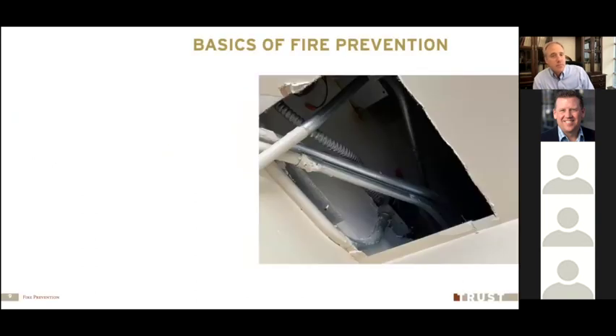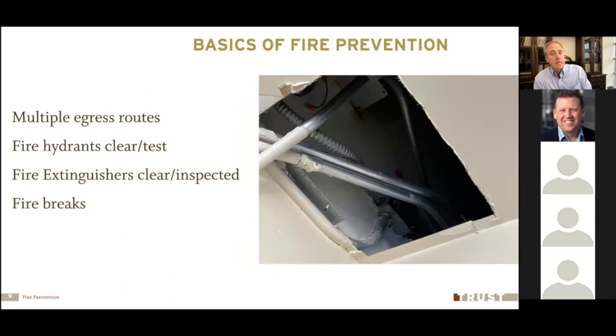Another basic one that we see a lot is the hole in the ceiling, the fire break, that drywall on your ceiling. It should be an extra thick sheet of drywall to help stop fire spreading from a room into the rafters and traveling through other parts of the building. And so we often see where holes have been cut into the ceiling or where panels have been removed to do repair work, to pull wires, whatever reason.